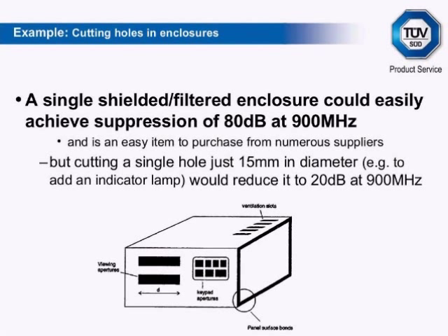A single shielded filtered enclosure could easily achieve suppression of 80 dB at 900 MHz. However, cutting a single hole just 15 mm in diameter — for example to add an indicator lamp — would reduce it to 20 dB at 900 MHz. Shielding is very easily compromised by cutting holes to run cables, pipes, lamps, and other items through the enclosure skin. Further compromise can be caused by incorrect termination of cables, even through an EMC gland if not utilised correctly.